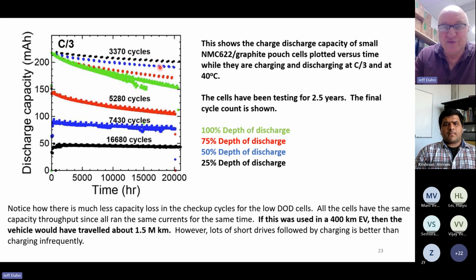The same is true for 50 and 75%—it's better to do these repeated small depth of discharge cycles as opposed to a lot of 100% depth of discharge cycles. One thing to remember is all these cells after 20,000 hours have passed the same amount of charge in the charge and discharge directions, and doing the small depth of discharge cycles leads to much better capacity retention.